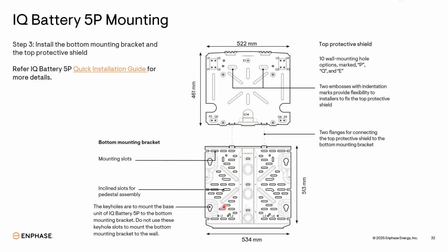These are mounting plates. This is the bottom plate. The bottom plate is the load bearing plate, so the complete weight of the battery this plate will bear. For mounting this plate we have holes provided here. What we recommend is to use minimum 7 fasteners, M8 fasteners you can use. So four on all four corners, and three in between these. You can mount this on a wall, and we also have a ground mounted bracket, a floor mounted bracket also available. You can mount there also.